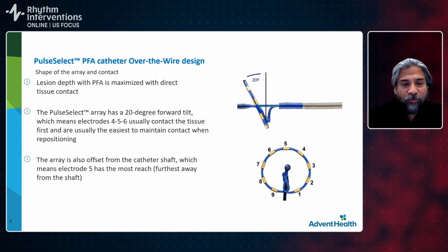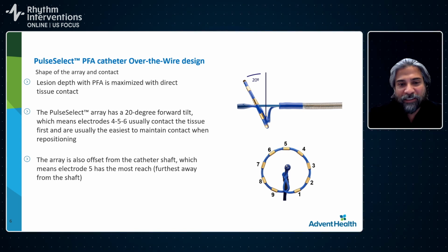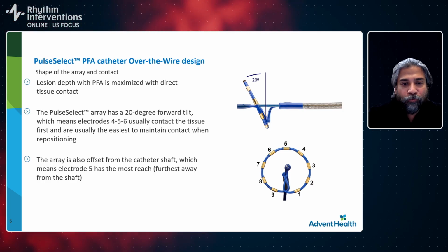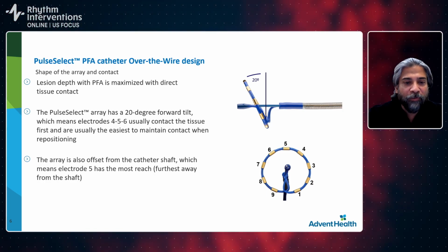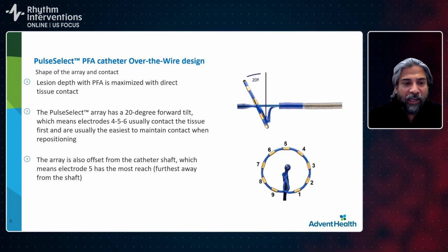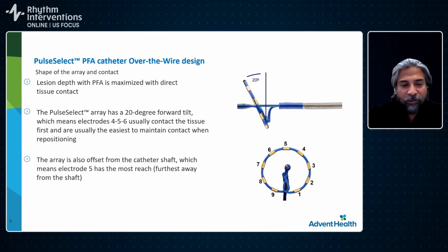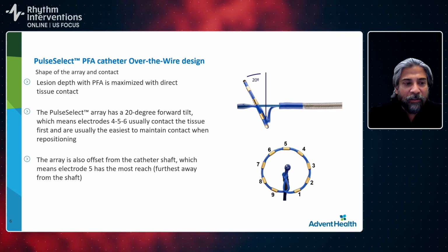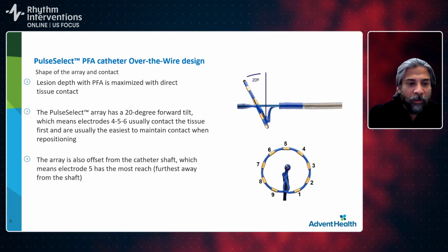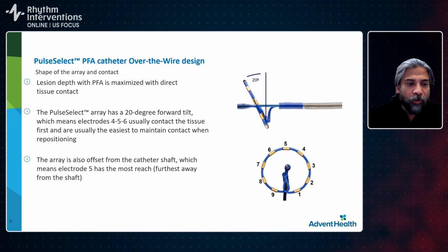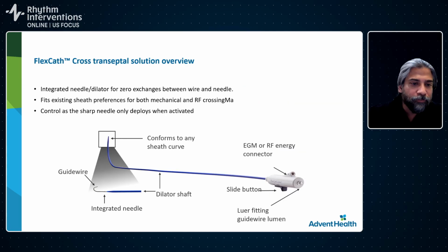The lesion depth, as we all know and are learning more and more, is maximized with direct tissue contact. So electrodes 4, 5, 6 are the ones which are in maximum contact, and we tend to tag those on our map, as you heard previously in one of the other talks. And then that helps us maintain contact when repositioning. And electrode 5 tends to have the furthermost reach.